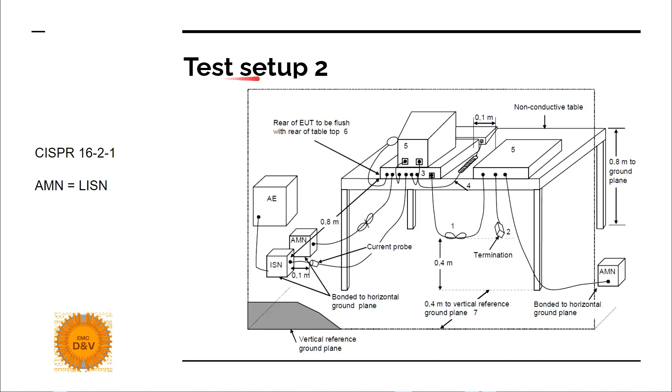Test setup number two is also an example of benchtop device testing, but with two metal walls, one in vertical position and second in horizontal position. This gives you an opportunity to put your LISN or AMN, artificial mains network, on the ground on the metal reference horizontal plane. Then you will have more space on your table to measure your device and auxiliary equipment.